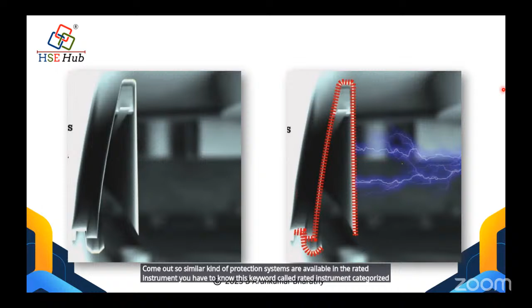One thing. And the other thing is that a certified equipment is protected against arc from transients. Now we saw that, right? Surge, lightning and load switching. It will have an independent certification and a protection. Like category 3, if the person is using it at 1000 volt, or category 4 at 600 volt, the voltage may be different, but the protection will be the same for both voltages. It means if I am using an instrument for category 3 at 1000 volt, I have to use the same instrument in a category 4 location, but the voltage should be limited to 600 volt. Then only this protection will help me. See, what is my protection here? The fuse will blow. That's it.